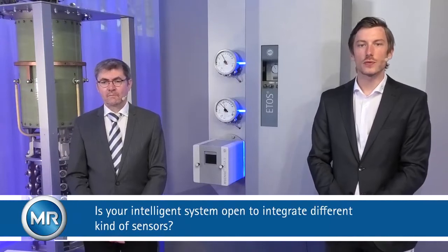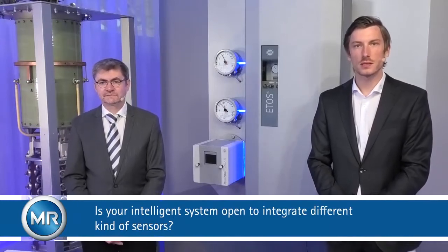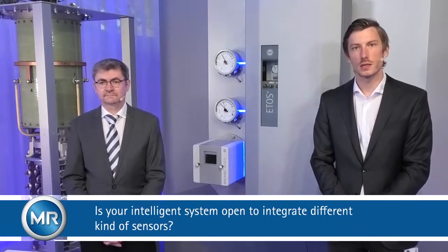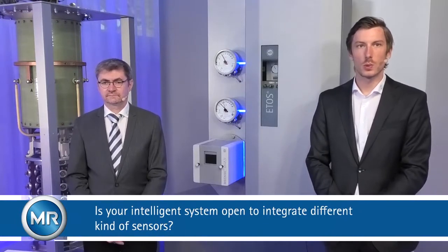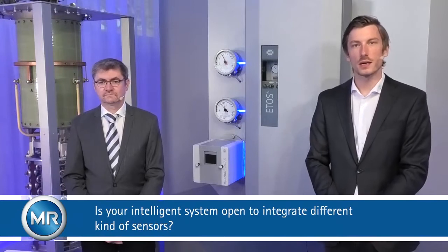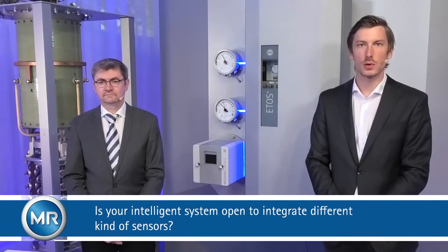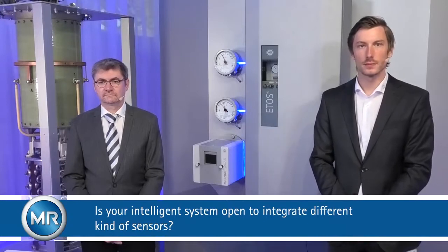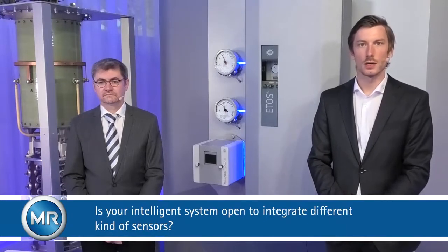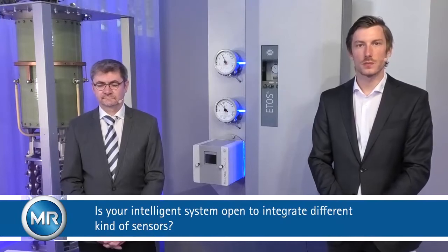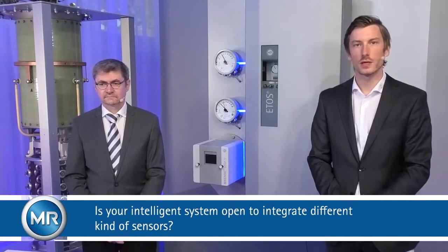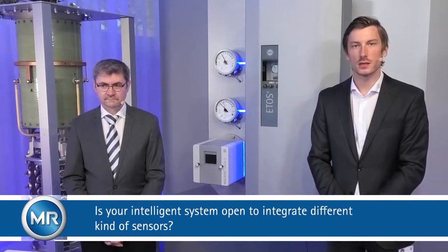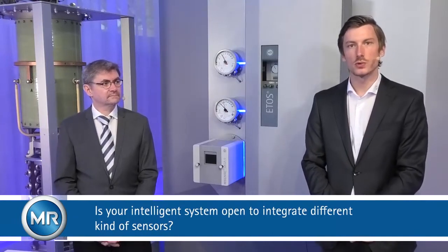And in terms of the MR sensors, the MSENSE, it's pre-configured. What does that mean? It means that when you, for example, have a DGA sensor or an M-trap or a bushing monitor or a temperature monitor, it's pre-installed, pre-configured in ETOS, and it's basically just connecting the Modbus system to ETOS.